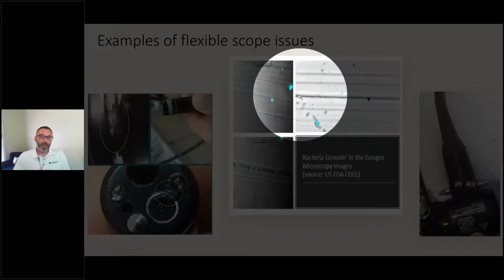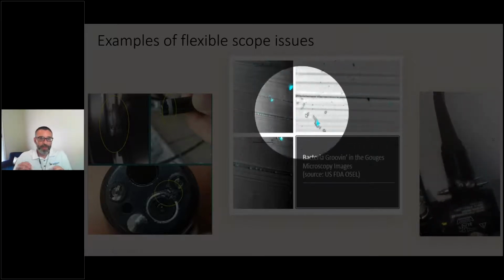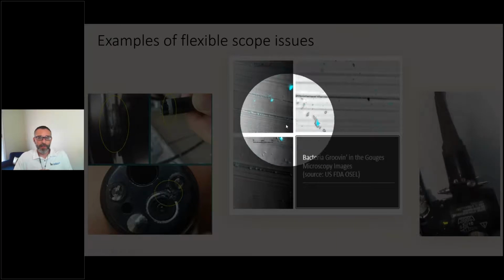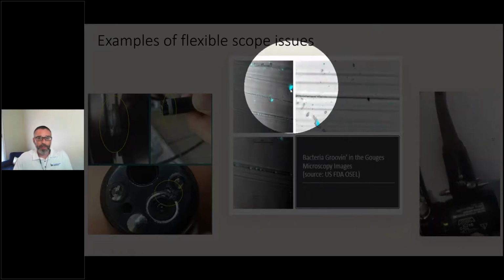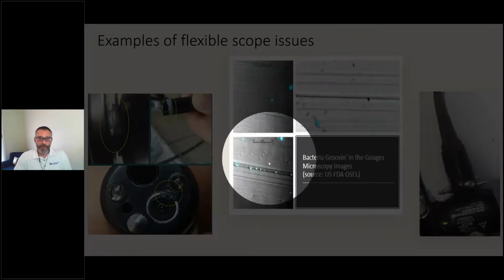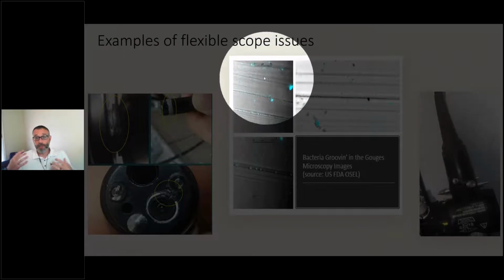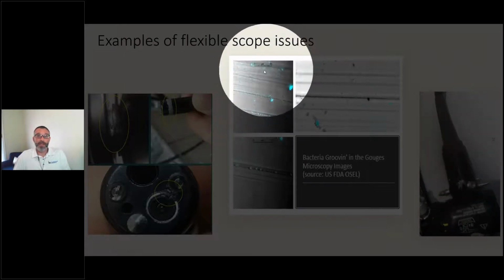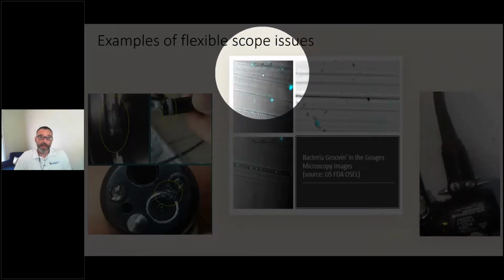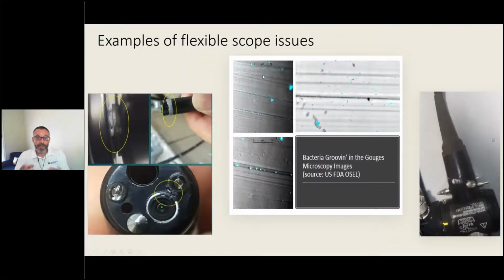Here's the scary part. They put some dye in there, and these little blue specks are microbial contamination. So when the FDA says you should be doing some kind of contamination testing, are you checking for gram-negative bacteria and things like that? This is why. That's how they live inside an endoscope, even when you're cleaning it and trying to clean it properly and disinfecting it.